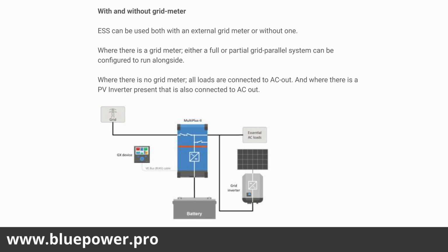And you're not feeding any non-essential loads. So if you've got any non-essential loads in this case, they might be connected to the AC output too, but they still don't exceed 5 kVA on your 5 kVA inverter, or 10 on your 10.